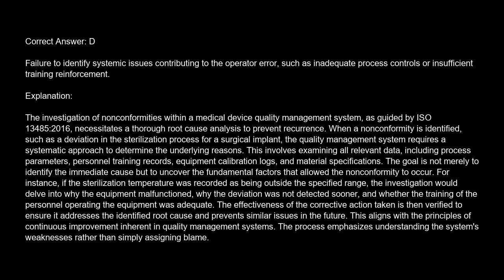This involves examining all relevant data, including process parameters, personnel training records, equipment calibration logs, and material specifications. The goal is not merely to identify the immediate cause, but to uncover the fundamental factors that allowed the nonconformity to occur.